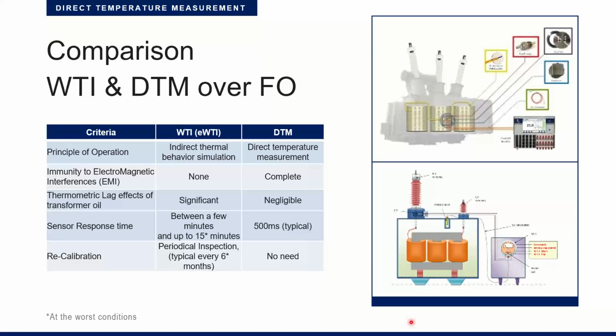The thermal lag effect of the transformer oil is significant for the winding temperature indicator, and it's negligible for the direct temperature monitor. The response time is between a few minutes and up to 15 minutes, plus the lag effect of the oil, for the winding temperature indicator, and only 500 milliseconds for the direct temperature monitoring. Recalibration is needed for the winding temperature indicator and not needed for the direct temperature monitor.